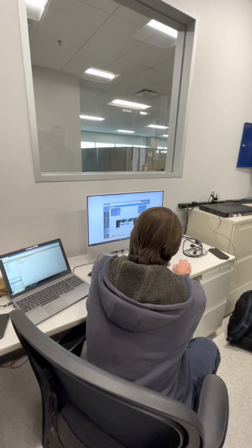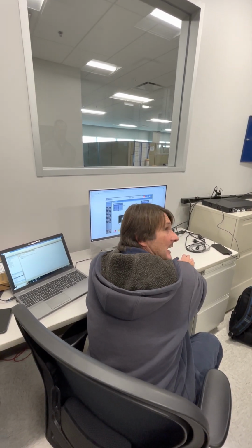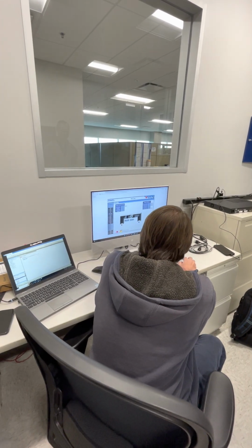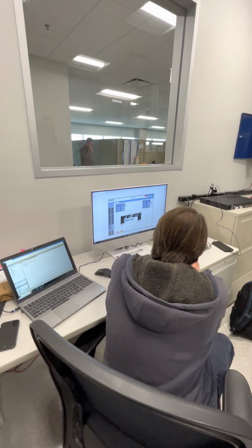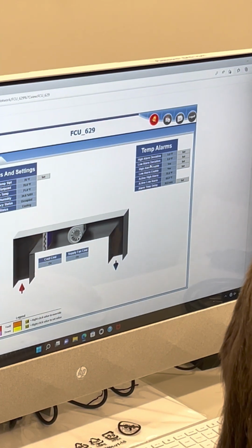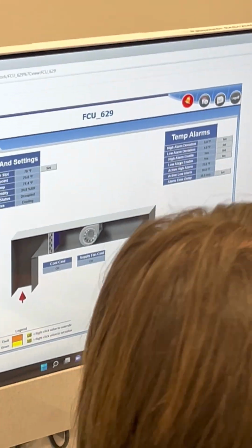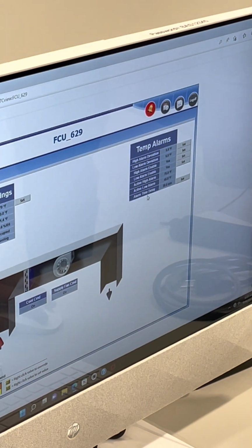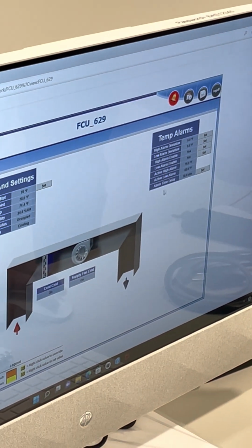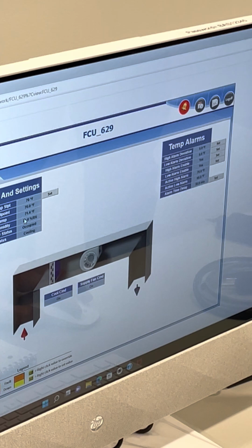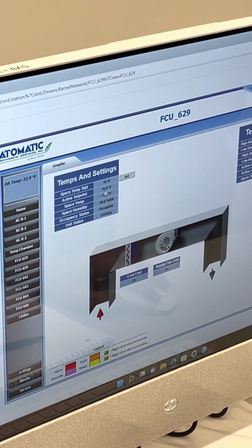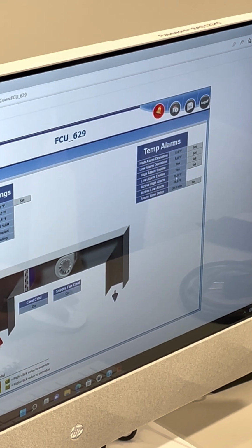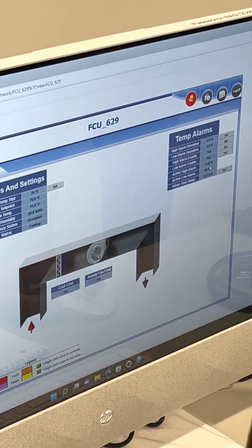Also, you have space temperature alarms. These are what are getting emailed out to us every once in a while. So right now you have high alarm deviation, low alarm deviation. You can enable it, disable it, whatever you guys want to. I have them both enabled at the same time. And then also a time delay. As you can see right now, our active set point is 70 degrees, so I have a plus minus of 5 degrees on all of that. That spits back to you and tells you what your high and low alarms are.